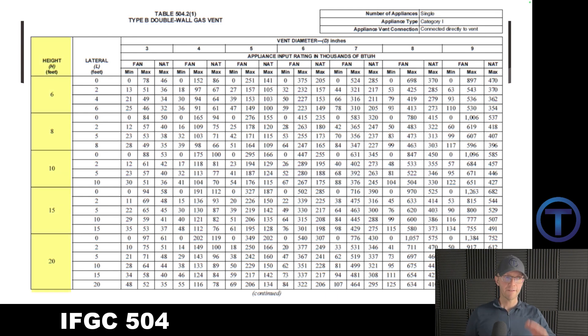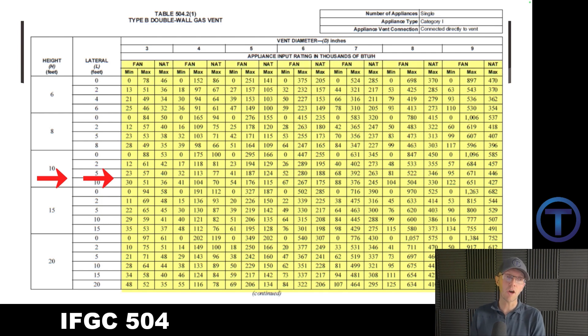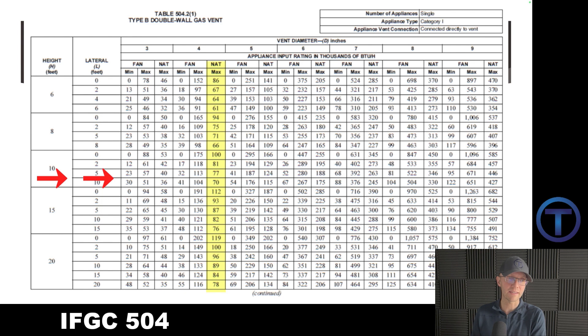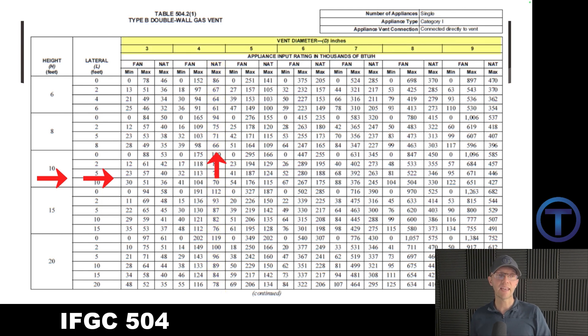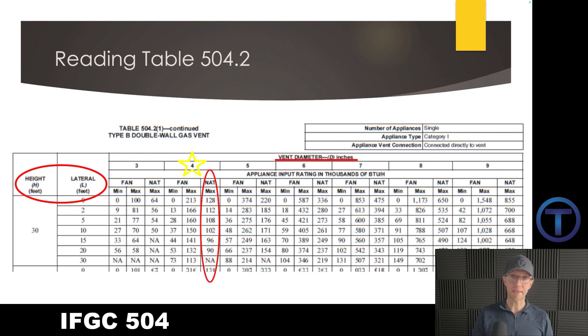Let's break this down. Far left column: the height of the vent. Second column: the lateral, or horizontal travel of the vent. Then there's a big open area with lots of BTU values — that's where I look with my BTUs. I need to narrow that down to the columns that are natural draft vent, for most everything we're doing as plumbers. Once I find my BTUs in a column of natural draft vent, I come up to the top. Vent diameters are listed across the top of that table — that's how I find my size.